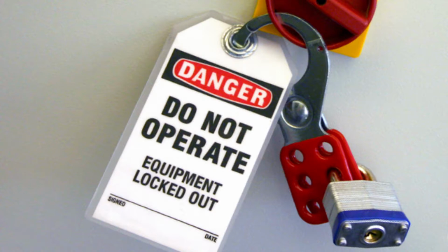Lockout tagout. Safety equipment required during the procedure will be designated by the qualified person and is dependent upon the potential hazards involved. The confined space will be completely isolated from all other systems by physical disconnection, double block and bleed, or blanking off all lines. Blanks used to seal off lines will be capable of withstanding the maximum working pressure or load of the line with a minimum safety factor of 4.